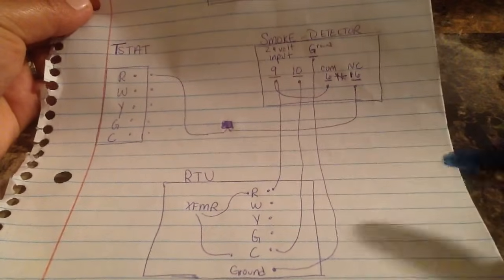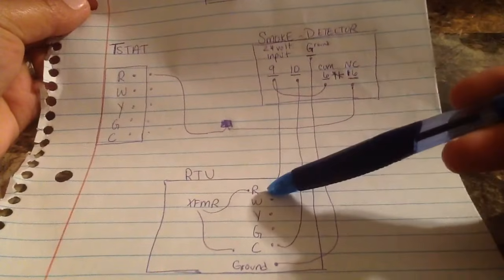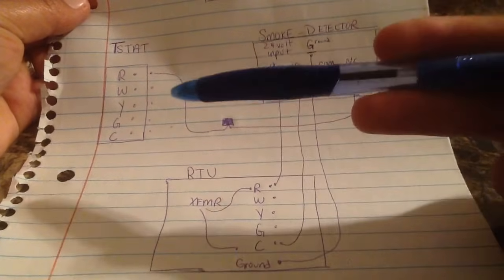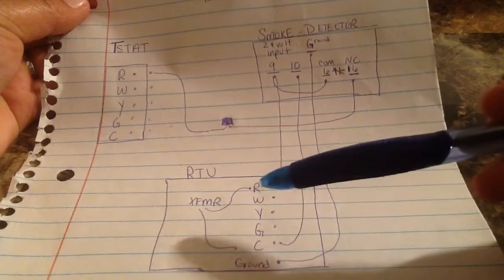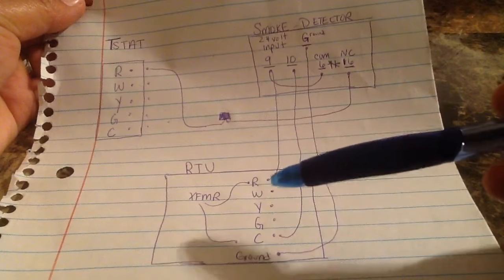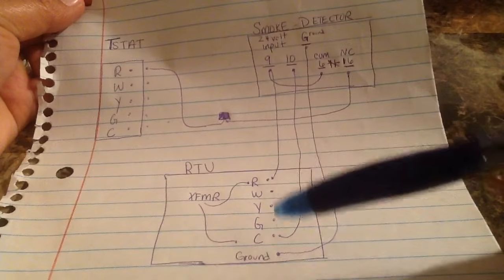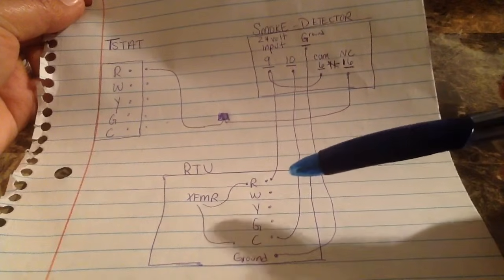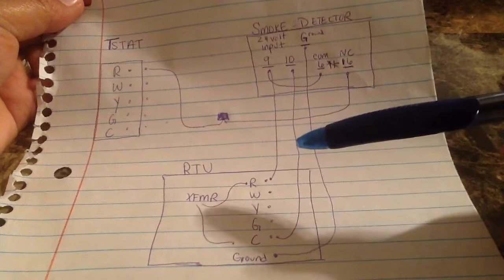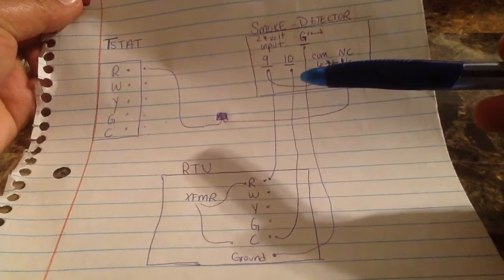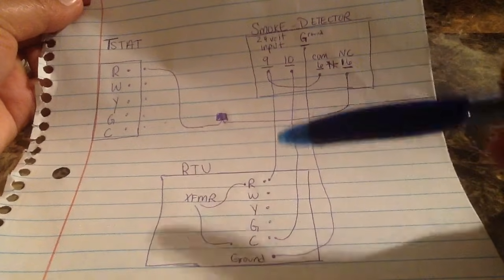So over here we have our rooftop unit, you got your smoke detector and you got your thermostat. Here at the rooftop we have our transformer, our transformer provides 24 volt to R and C. What you're going to do is run an eight wire conductor from the rooftop to the smoke detector. I'm only using four of those wires, the other four stay for spares.